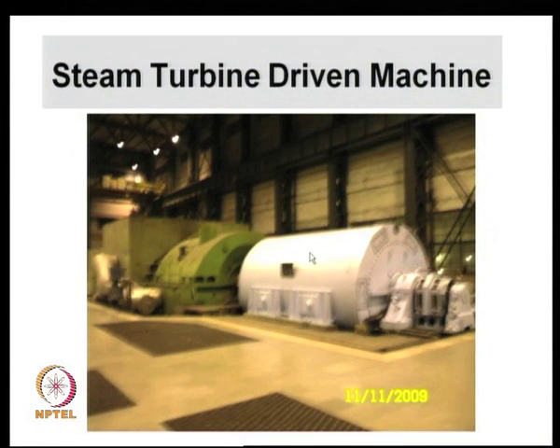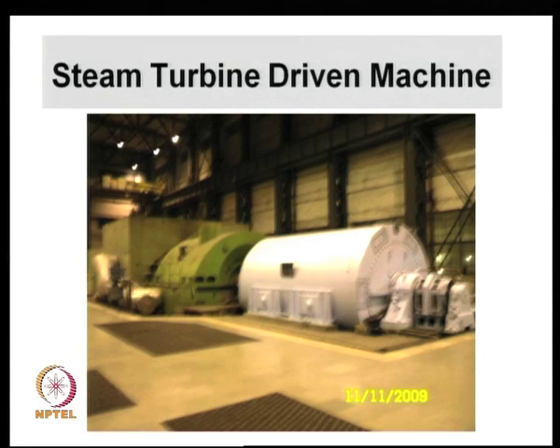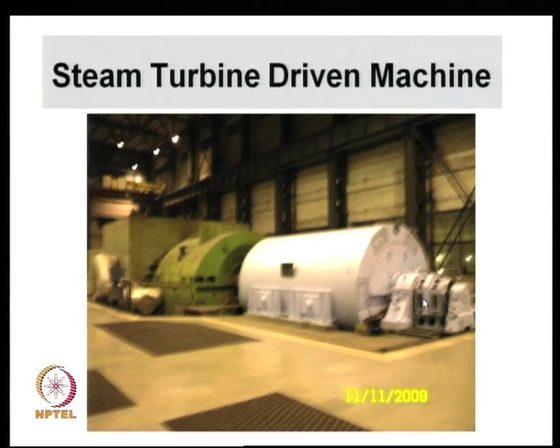It will be instructive to first look at how a practical synchronous machine looks like. What I will show you right now is a steam turbine driven generator of around 210 megawatts. What you see in white is the synchronous machine; in green are the various stages of the steam turbine. On the side are the bearings, and at the end are the slip rings and brushes which convey the excitation voltage to the field winding rotating in this synchronous generator.